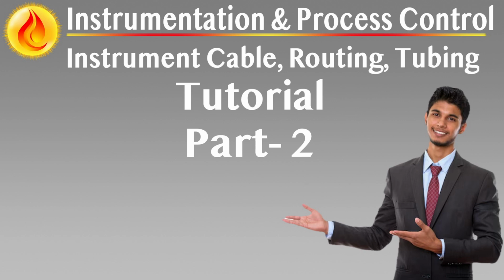All cable sections within a trench must be pulled in a single continuous operation. If interruptions are unavoidable, the trench must be temporarily covered with steel plates to prevent exposure or damage. Cables must be laid in unbroken lengths between termination points to avoid unnecessary joints, which introduce potential failure points.